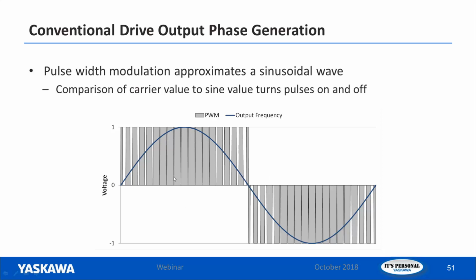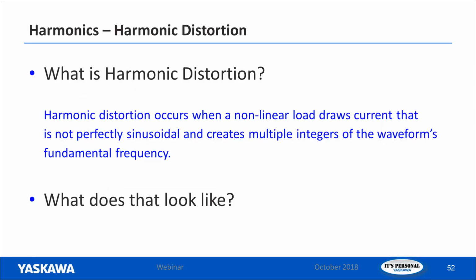Now the problem is, as these pulses are created, that goes back through the VFD and back out onto the line voltage, and that's where you can get your distortion. So what is harmonic distortion? I'm going to read what we'll call the clinical definition here for you. Harmonic distortion occurs when a nonlinear load draws current that is not perfectly sinusoidal and creates multiple integers of the waveform's fundamental frequency. So let's take a look at what that looks like.